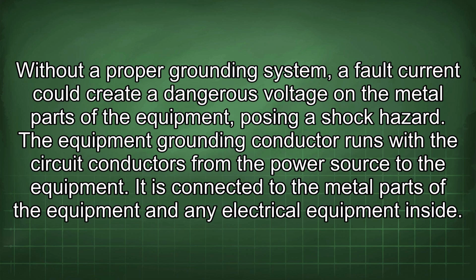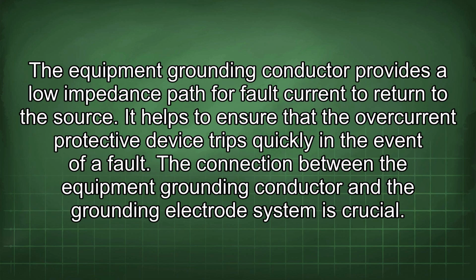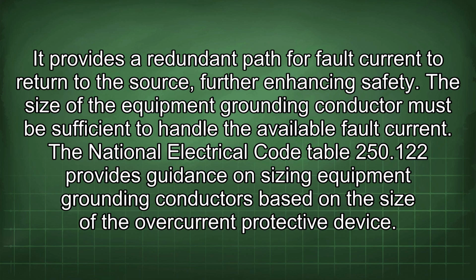It is connected to the metal parts of the equipment and any electrical equipment inside. The equipment grounding conductor provides a low impedance path for fault current to return to the source. It helps to ensure that the overcurrent protective device trips quickly in the event of a fault. The connection between the equipment grounding conductor and the grounding electrode system is crucial. It provides a redundant path for fault current to return to the source, further enhancing safety. The size of the equipment grounding conductor must be sufficient to handle the available fault current.